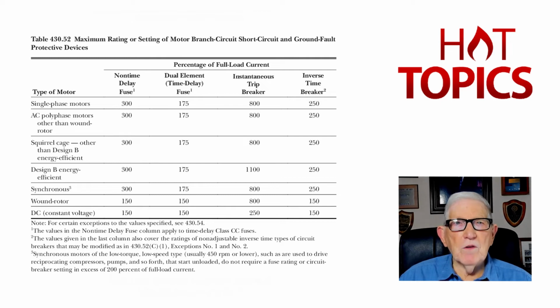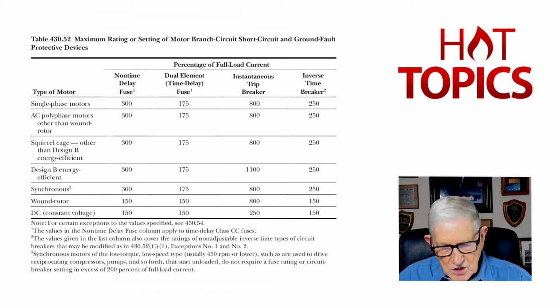First of all, what are the phases of the motor? Well, it's a polyphase, three-phase. So look at the type of the motor, column 1, Table 430.52, there on page 319, it looks like. Now, if we get the design of the motor, it was B, so you'll slide on down, and slide right across for a Design B, other than Design B, 250% now.